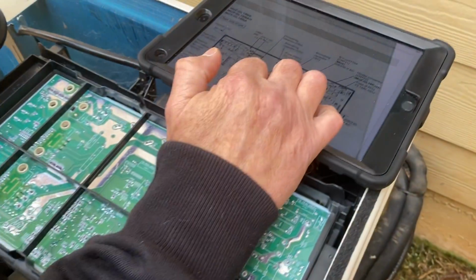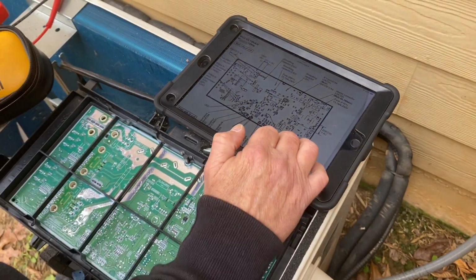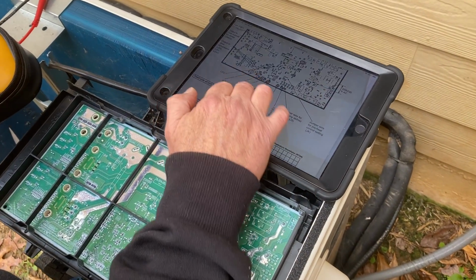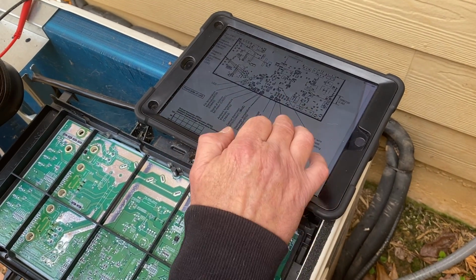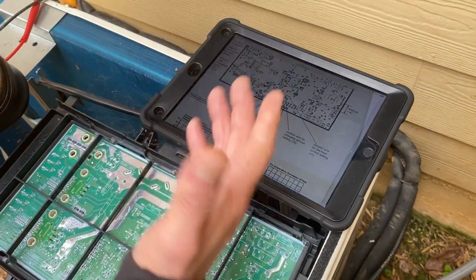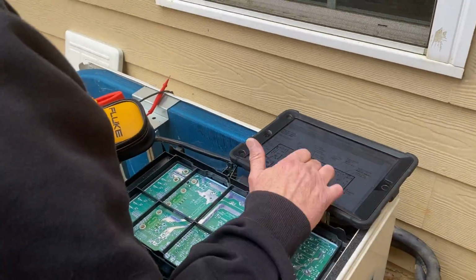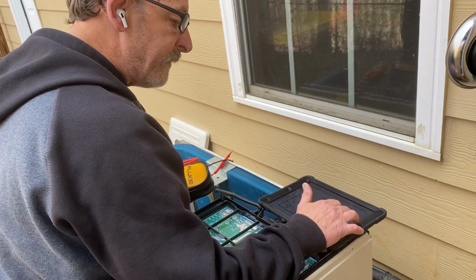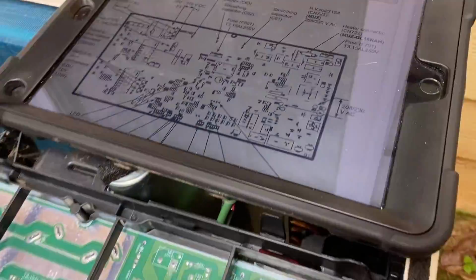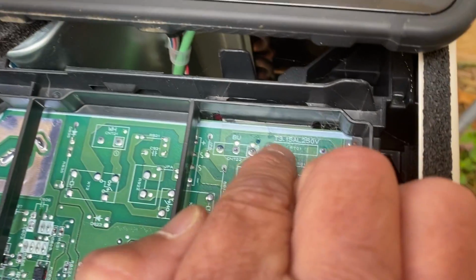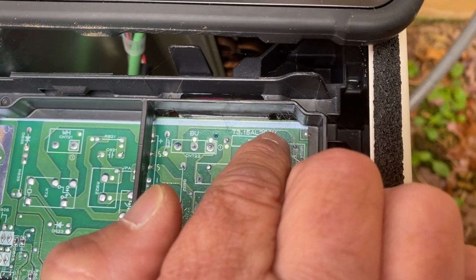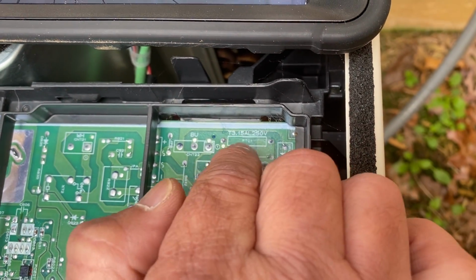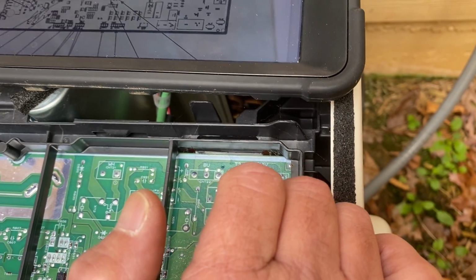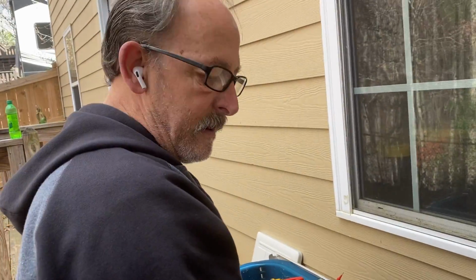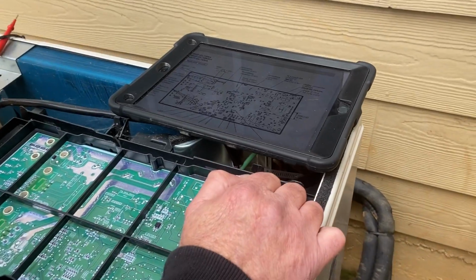If you're suspecting a fuse is blown, you could actually find fuse 801 or 701. We would have to find 701. And I apologize, I never prep for these videos. I just come out here, and here's CN7, here's your 701, this fuse right here. We could turn power on and take voltage on that pin right there and that pin right there. If you didn't have voltage, we would know that fuse was good. But if you had voltage on one side, that would mean that your fuse was bad. So you would know that that fuse was bad on this board.